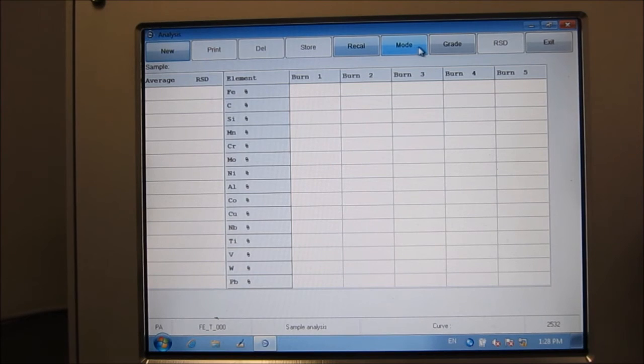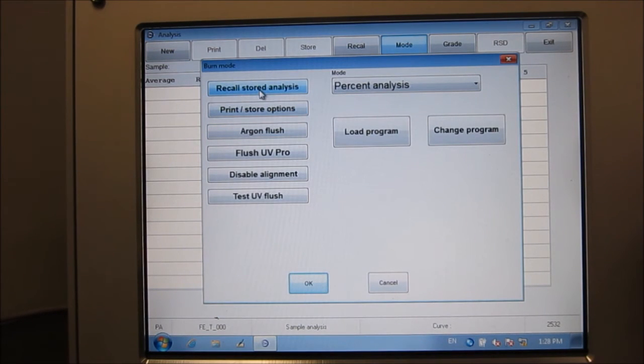Okay, now go on to mode. As I've shown you just now, recall stored analysis will be to recall some of the stored measurements. This is to print. Then you have argon flush and UV Pro flush here. This is actually to flush the machine, that is the optical compartment with argon, and to flush the UV Pro is actually to flush the probe with argon.